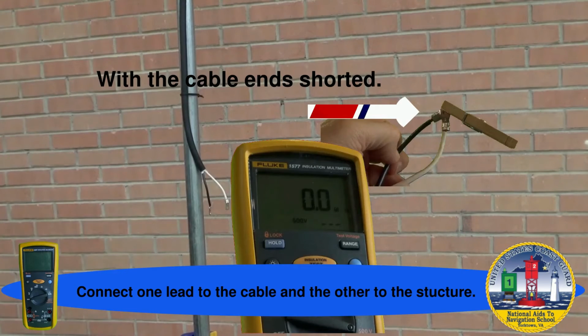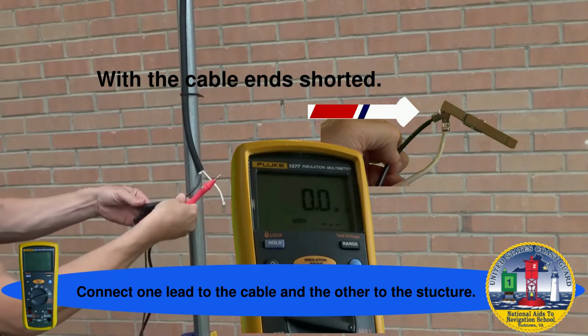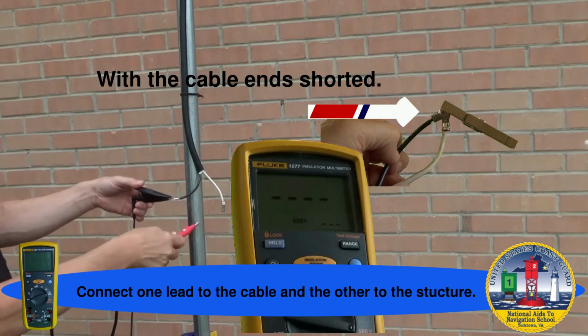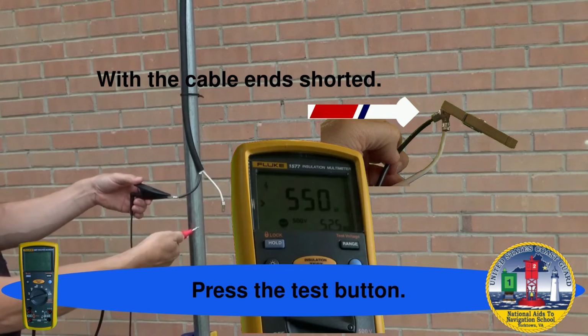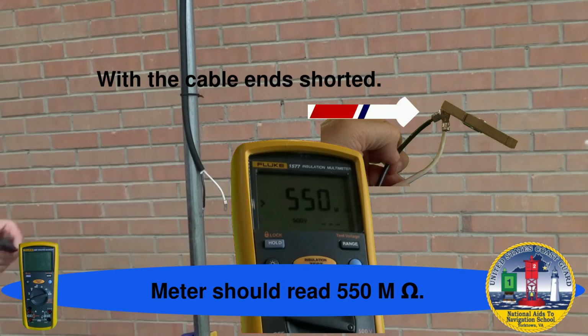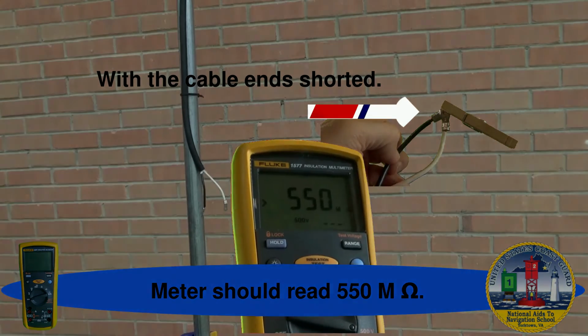At this point, the cable under test should still have one end shorted together. Connect one of the test probes to the cable and the other to the structure. Press the test button. The meter should read a high resistance. Note in your servicing guide, the resistance is only required to be greater than 1 megaohm.